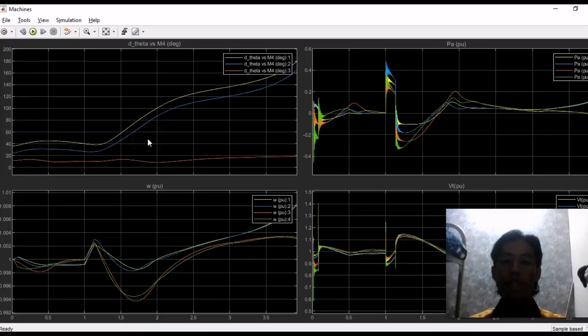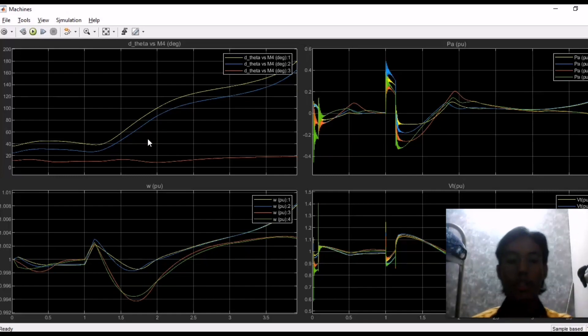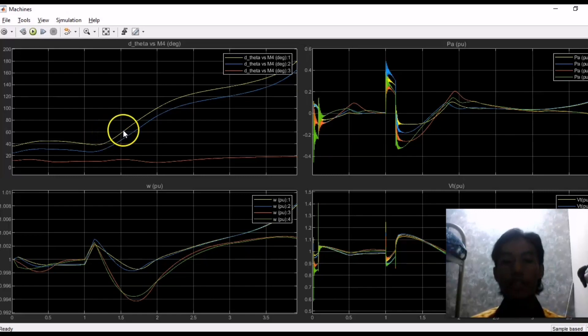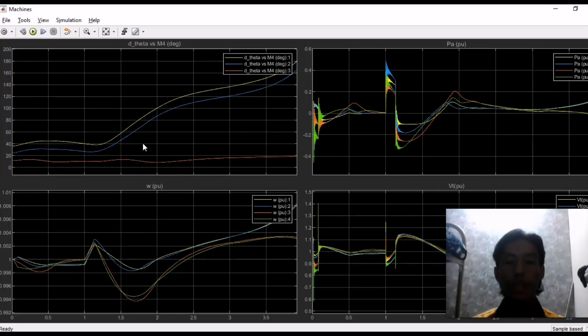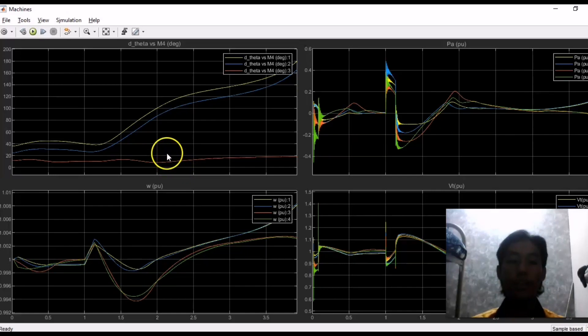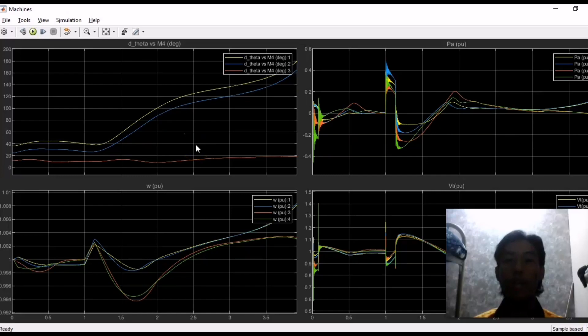When I run the simulation, we will get 3 types of graphs: rotor angle versus time, rotor speed versus time, and electrical power. For the first graph of rotor angle for the generator machine versus time, the yellow and blue represent area 1 and the red color is for area 2. Area 2 increased significantly and entered unstable condition when 150% load increment happened at bus 9. This happened due to the increased load demand occurring at generator 3 and generator 4 at area 2, which consumes real power from the generator, and more motor torque is required to generate electrical power to overcome the demand.